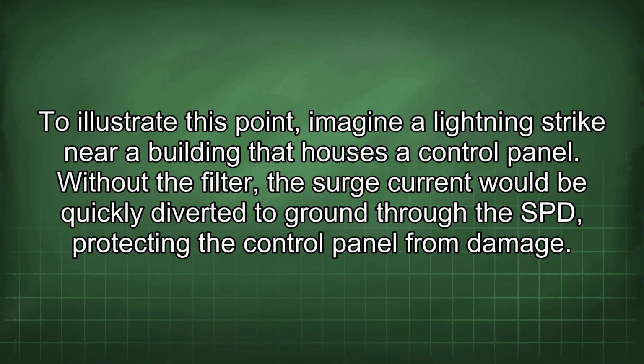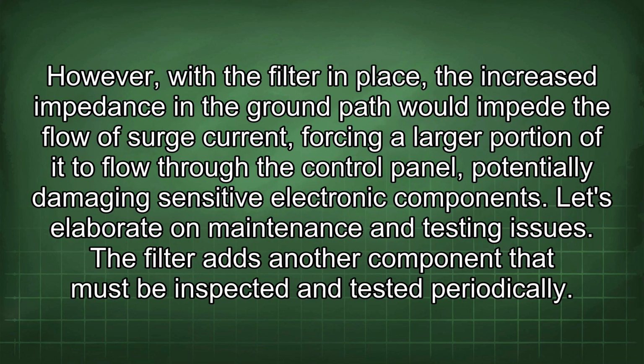To illustrate this point, imagine a lightning strike near a building that houses a control panel. Without the filter, the surge current would be quickly diverted to ground through the SPD, protecting the control panel from damage. However, with the filter in place, the increased impedance in the ground path would impede the flow of surge current, forcing a larger portion of it to flow through the control panel, potentially damaging sensitive electronic components.